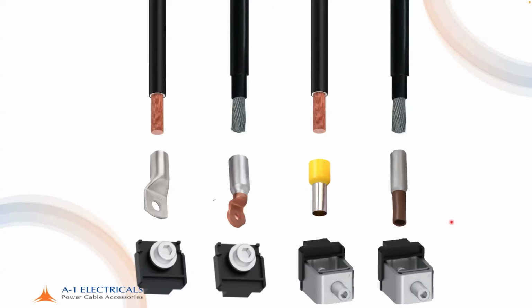See, I am not aware of what is widely being used, but I can tell you what is correct. If you have an aluminum conductor and you want to terminate it on an MCB or MCCB, there are different types of lugs depending on the kind of terminal. If it is a nut keeper terminal, you will need this kind of product. If it is a box terminal, you will need this kind of product. And the standard for testing this is, of course, IEC 61238, and you need to identify for the dimensions what the relevant DIN standard is and then make a selection.